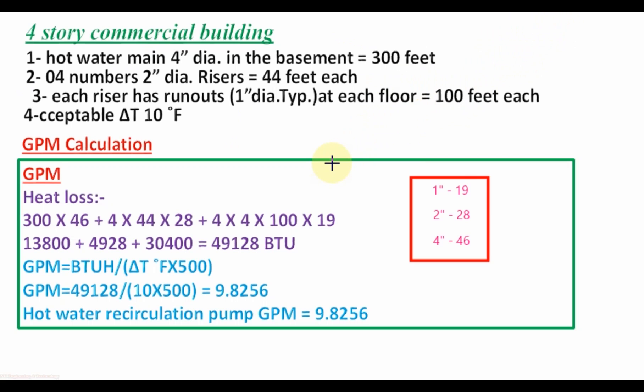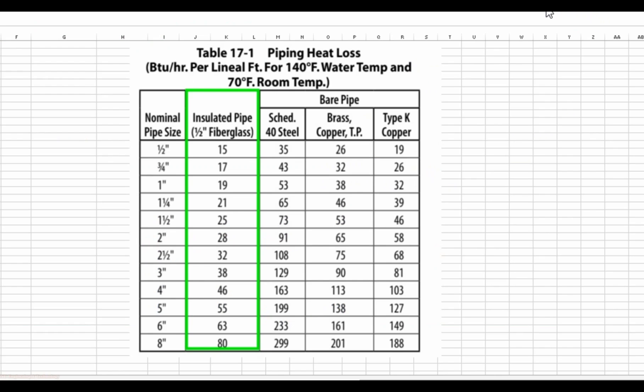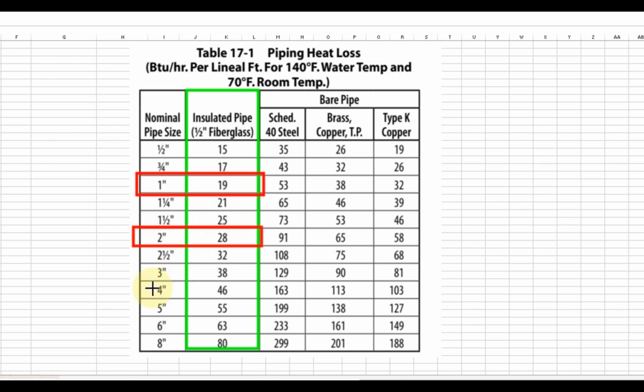To calculate the GPM for the hot water recirculation pump, first we will calculate the total heat loss in the hot water supply piping. From this table we will select the heat loss rate in BTU per hour per linear feet of pipe at 140 degrees Fahrenheit. For 1 inch insulated pipe, the heat loss rate is 19 BTU per hour per linear feet. For 2 inch pipe size it is 28, and for 4 inch pipe size it is 46.